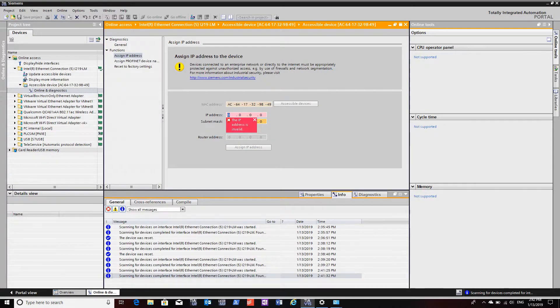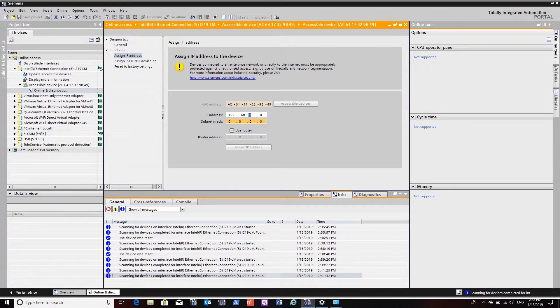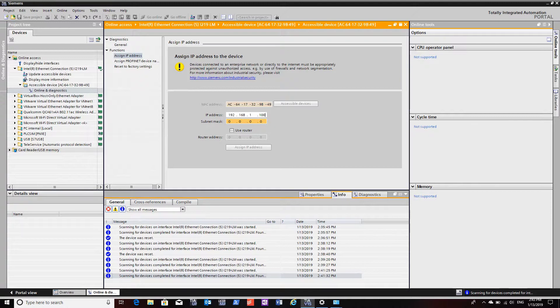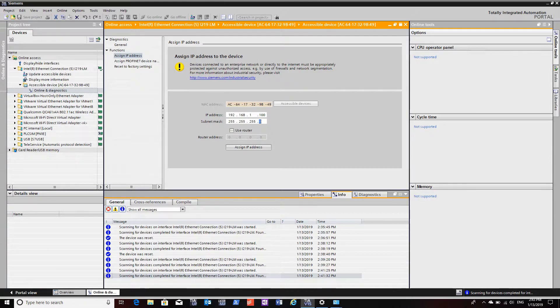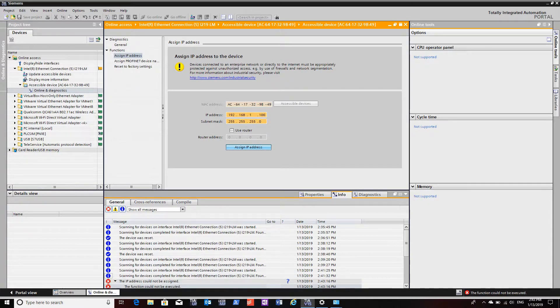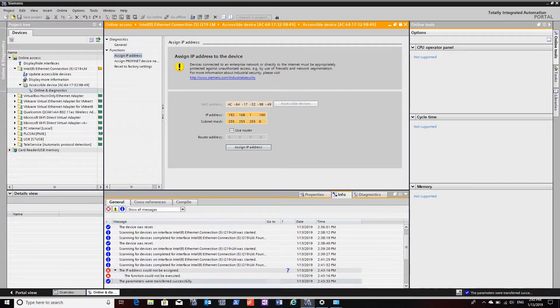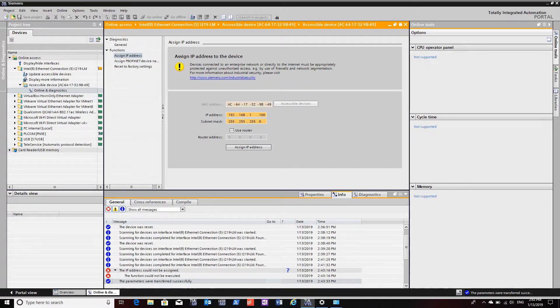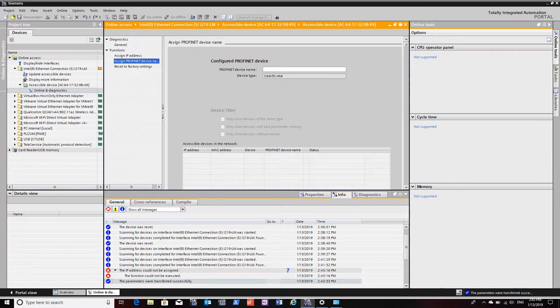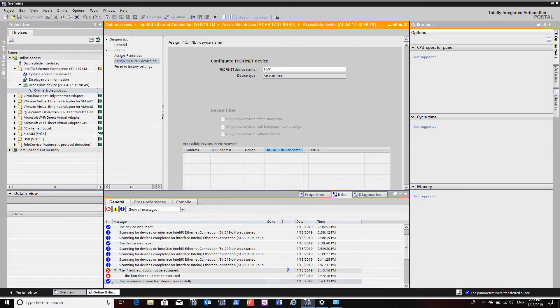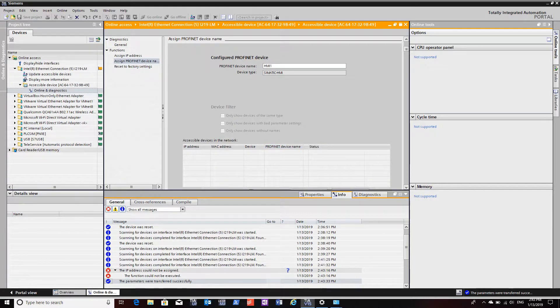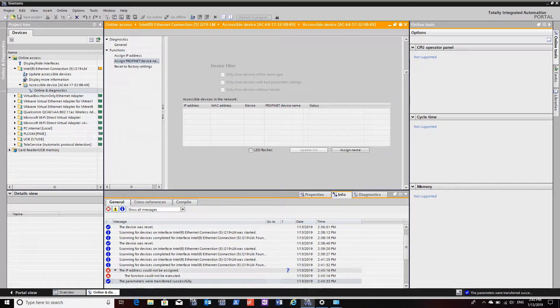So now fixed IP. I will put the display on the same network, standard subnet, not using a router. So I'll assign that IP address. Now with Profinet you also have to have a Profinet name. They're lowercase. Just give it a simple name. And I will assign it.